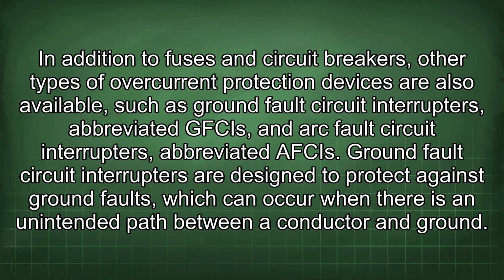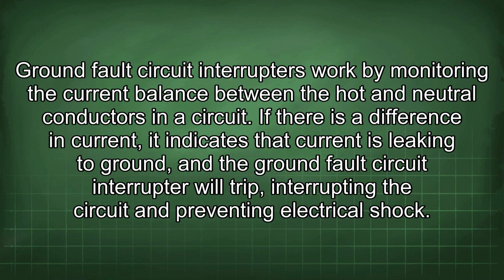Ground fault circuit interrupters are designed to protect against ground faults, which can occur when there is an unintended path between a conductor and ground. Ground fault circuit interrupters work by monitoring the current balance between the hot and neutral conductors in a circuit. If there is a difference in current, it indicates that current is leaking to ground, and the ground fault circuit interrupter will trip, interrupting the circuit and preventing electrical shock.